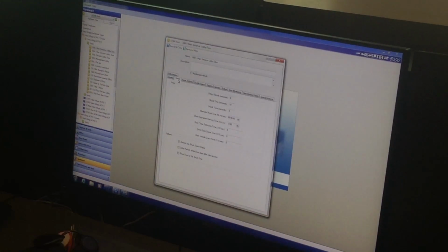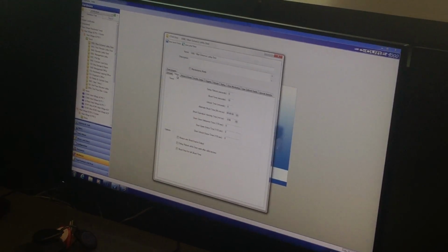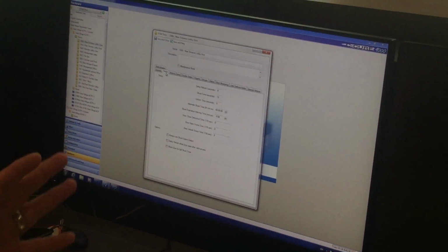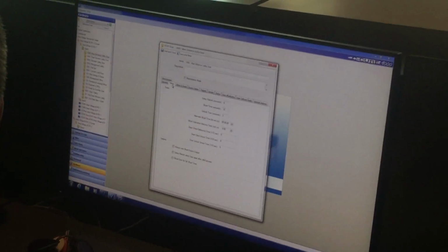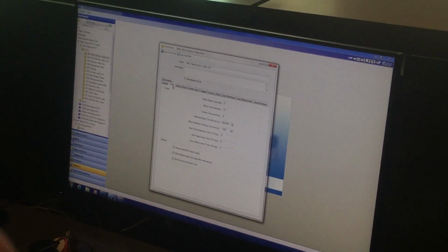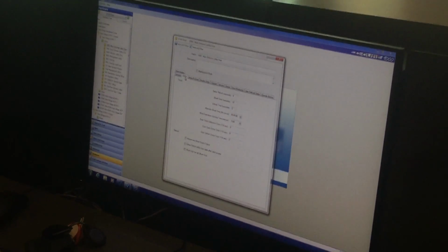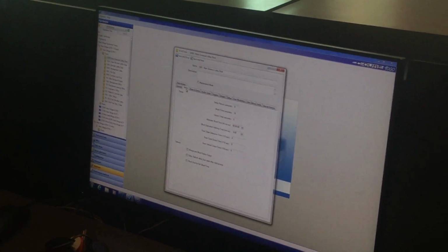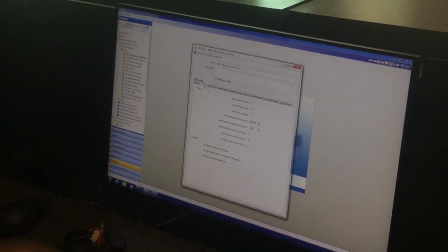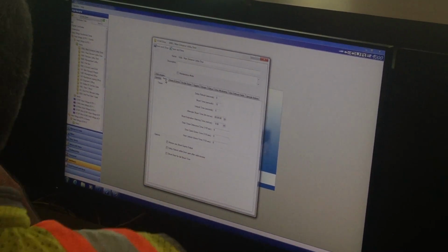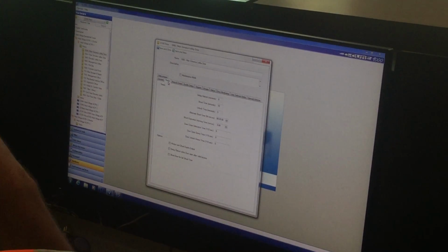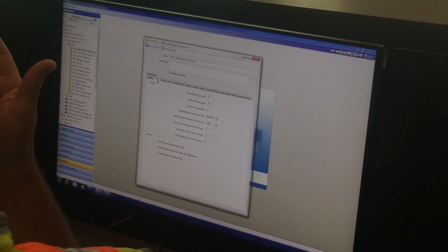Your timing may be something that y'all find you want to adjust on some doors. Like this one, I changed a little while ago because of building pressure and the closer. Before it would close, it would cause a door held alarm. The default on all the doors is 10 seconds. So if the door isn't shut within that 10-second time frame, it's going to throw a door held alarm.